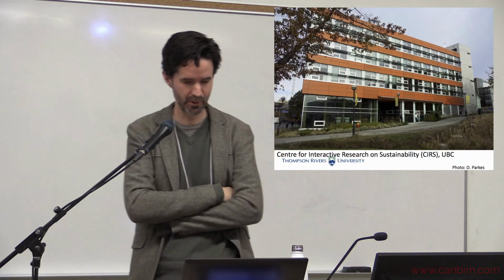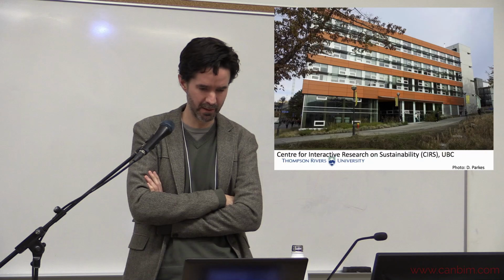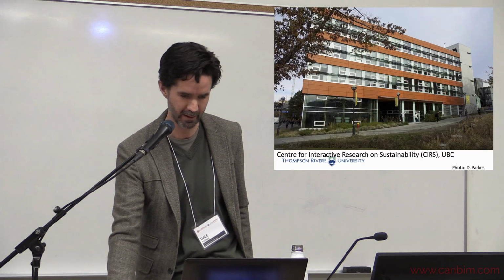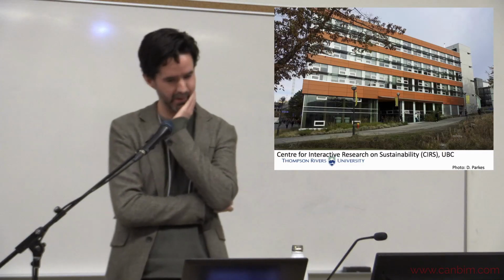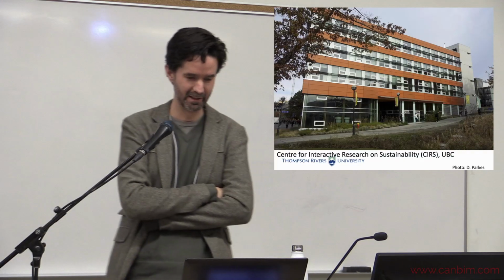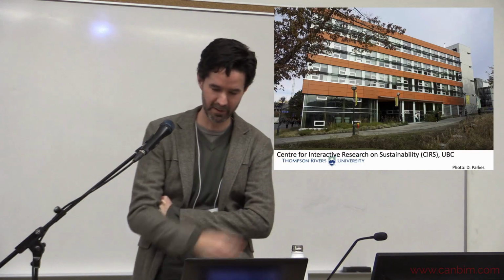Attempting living building certification, but also hasn't met the requirements yet. When we visited here a few years ago, they had some issues with their PV panel system. They used the solar panels for sun shading, and some of them had burned out, and they're wired in series. They have different technology now where you don't have to do that, but they couldn't figure out which ones were burned out, and it's very difficult to replace them all. Go and check them out. So yeah, they had some issues with that.